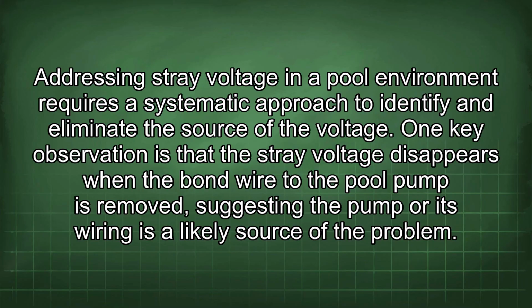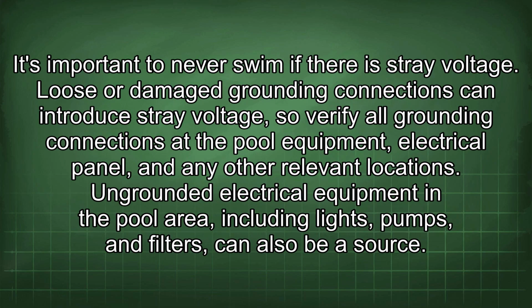Addressing stray voltage in a pool environment requires a systematic approach to identify and eliminate the source of the voltage. One key observation is that the stray voltage disappears when the bond wire to the pool pump is removed, suggesting the pump or its wiring is a likely source of the problem. It's important to never swim if there is stray voltage.